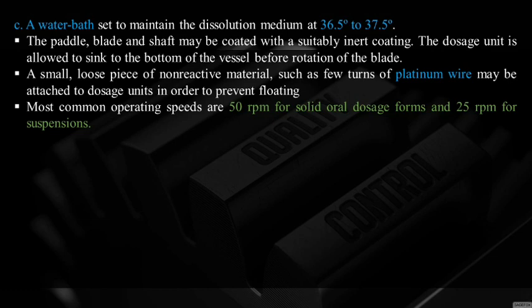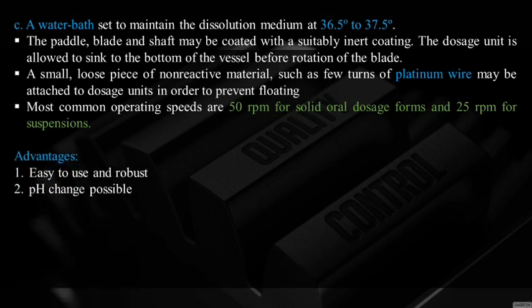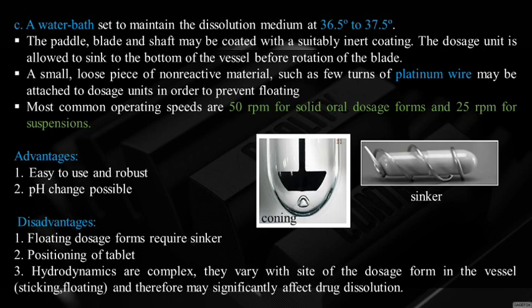Water bath maintains dissolution medium at 36.5 to 37.5°C. The paddle blade and shaft may be coated with a suitably inert coating. The dosage unit is allowed to sink to the bottom before rotation. A small piece of non-reactive material such as a few turns of platinum wire may be attached to prevent floating. Most common operating speed is 50 rpm for solid oral dosage forms and 25 rpm for suspensions.